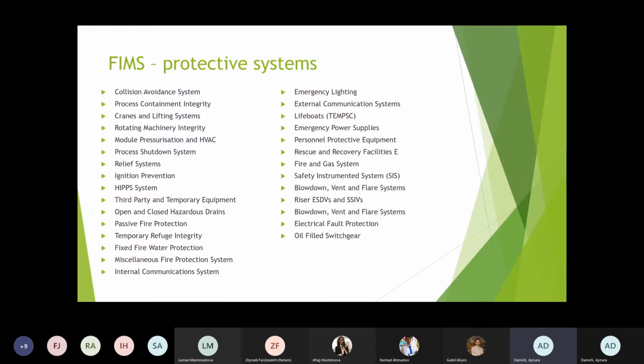So rescue and recovery facilities, to provide a rescue and recovery provision for persons who have to evacuate or escape from the installation, or who require rescue near the installation from reasonably foreseeable events. Fire and gas system. The goal is to continuously monitor designated areas of the installation, and upon detection of a fire or an accumulation of flammable gas or smoke, to initiate alarms and provide output signals to field devices which initiate a rapid and appropriate response in accordance with the fire and gas cause and effect charts.